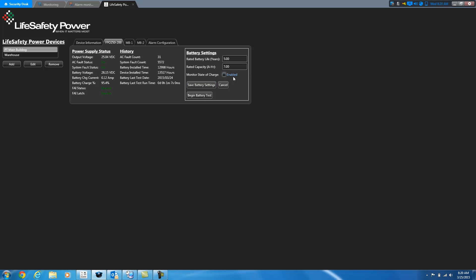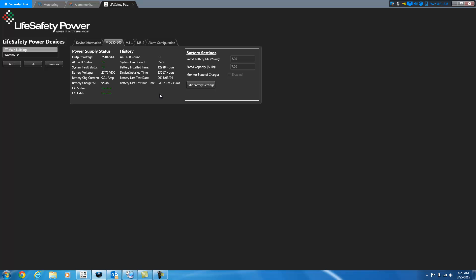If I turn off monitor state of charge, a couple of things occur. One, the begin battery test button is going to disappear. So it's gone now, so you can no longer run a battery test. And you may or may not get battery charge information. You must also have a current sensor hooked up between the battery and the power supply board in order for all of this to work properly. And those current sensors you can get from Life Safety Power. So I'm going to go ahead and turn the state of charge back on so that I can run a battery test and show you how that works.